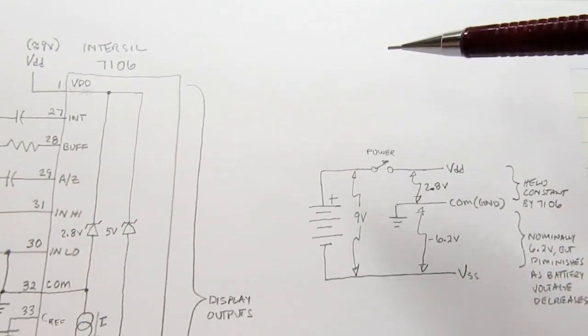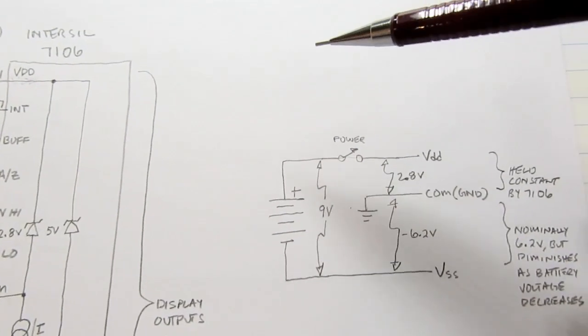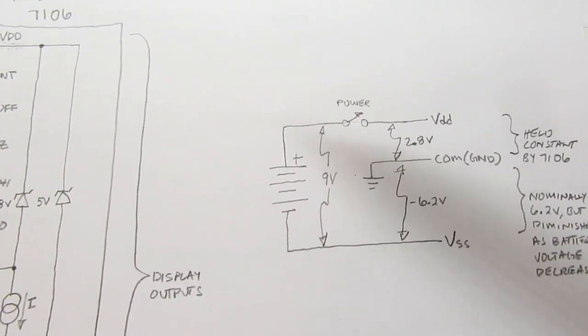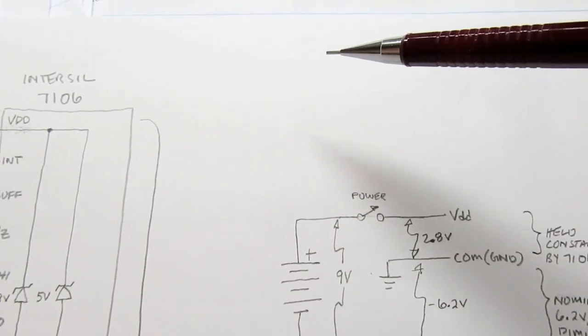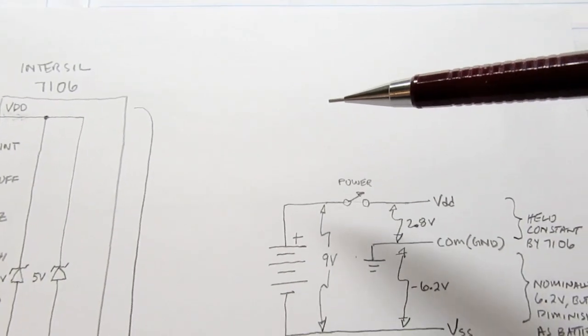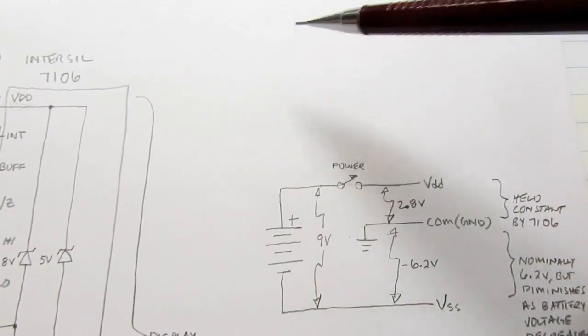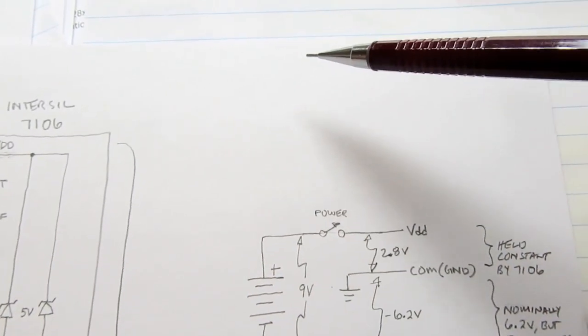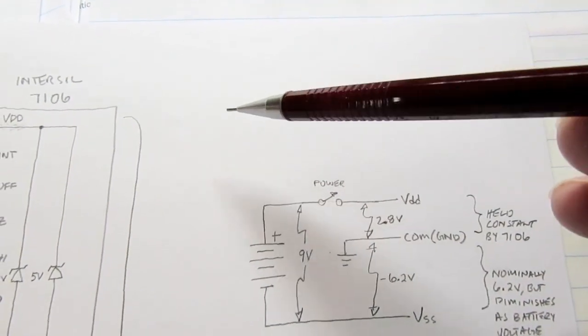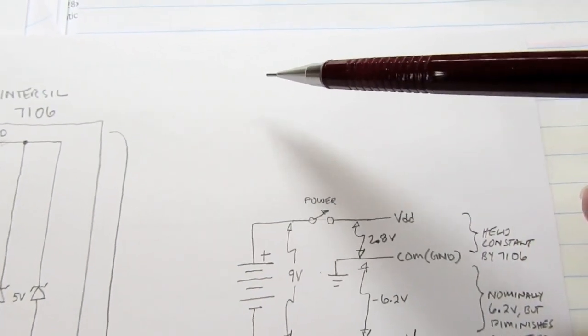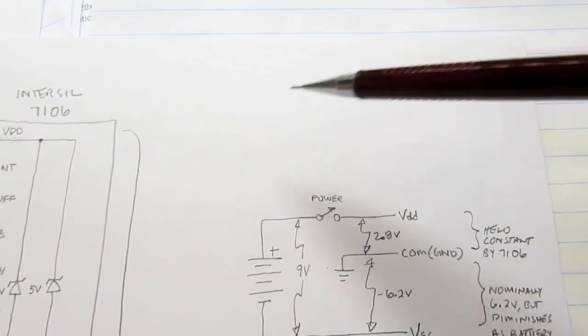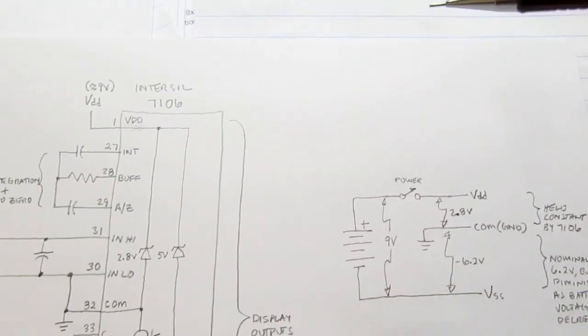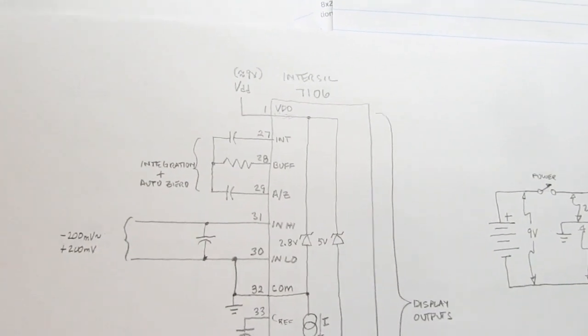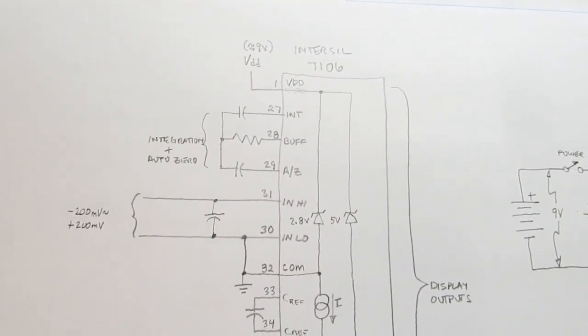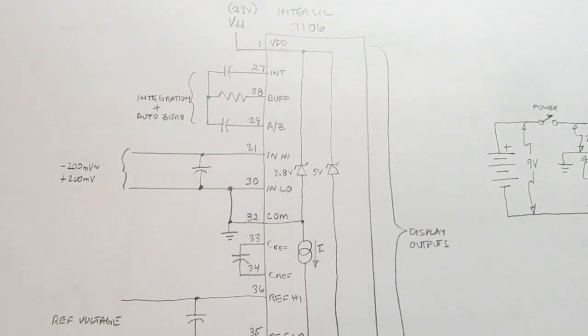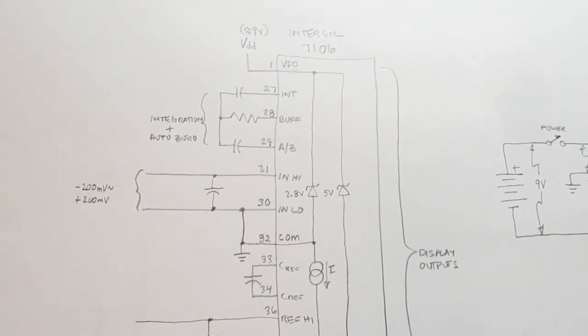So that's a single slope, but it has problems. It works, but it's not as stable. It doesn't compensate automatically for variations in values of the components in the integrator circuit, so it's not as good. With the dual slope method, you ramp up and then you ramp back down, and then ramp up and ramp down again, and different tests are done on the up slope and the down slope, and by doing so the circuit that surrounds that is able to compensate for drift. It can compensate for power supply voltage differences and temperature and all sorts of things, and it just makes for a more stable, accurate multimeter.